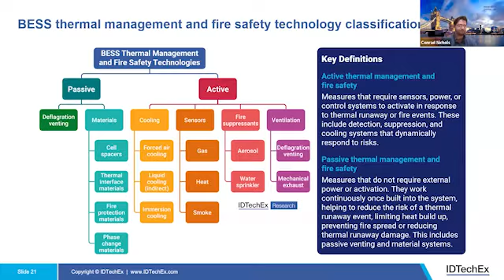Thermal management and fire protection technologies for BESS can broadly be split into active and passive systems. Active technologies refer to systems which require power to operate and dynamically respond to risks, such as cooling technologies, sensors, fire suppressants, and ventilation. Passive technologies mainly relate to material systems which do not require external power or activation, and instead work continuously once built into the system to reduce thermal runaway risk, control the extent of damage, or provide fire retardant properties.